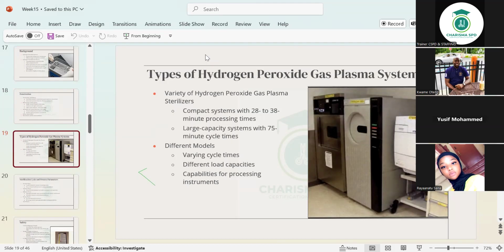But then there are Compact systems, whose cycles are about 28 to 38 minutes. The one at my job is between 45 and 50 minutes. Once in a while, depending on the amount of load in it, even if it's not overloaded and it's up to its capacity, at times it goes to 52 or 53 minutes. But ideally it's between 45 and 50 minutes. So it's within range. The large capacity systems, as per this book, have 75-minute cycle times. The different models have varying cycle times.